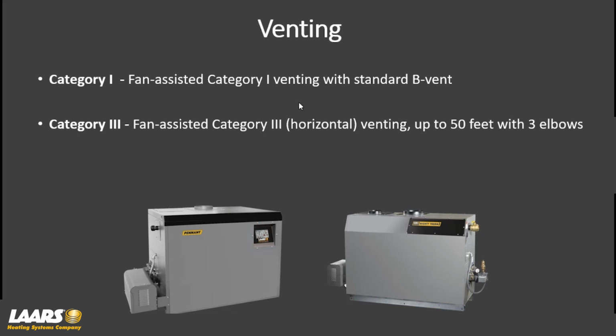So for Cat 1, we can use standard B vent. Again, vertical rise. As we're heating that chimney liner, we'll refer to this as B venting. What happens? We actually create a greater draft. So we could overdraft the appliance. Why I bring that up is in the manual, it states anything over 25-foot vertical rise, you have to add a barometric damper.